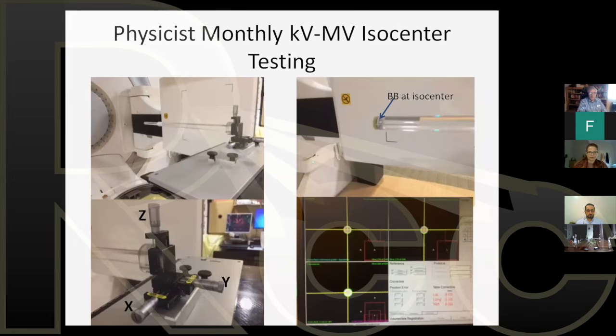I want to point out a very critical test. I know that the topic today was daily QA and IGRT. And I want to point out, however, a test on the Elekta Linac that is so critically important. And the same can be said for a Varian Linac too. There are different ways to run this test, but I'm familiar with Elekta, and this is the one that I'm going to show. And this is the physicist running a monthly KV-MV isocenter testing. I consider this one of the most important tests, along with output, flatness, and symmetry.